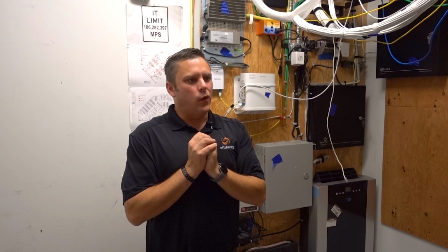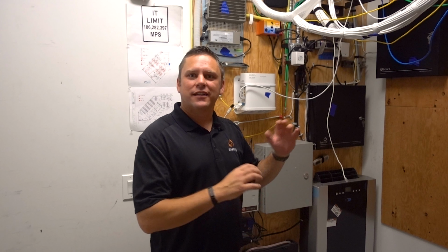Some access control systems will fail to the locked state, meaning when they get turned off, when they get disconnected, they automatically lock everything up and nobody's access cards will work anymore. You don't want to do that, obviously, if you and the rest of the moving team have an access card and you need to access this suite during the rest of the decommission.